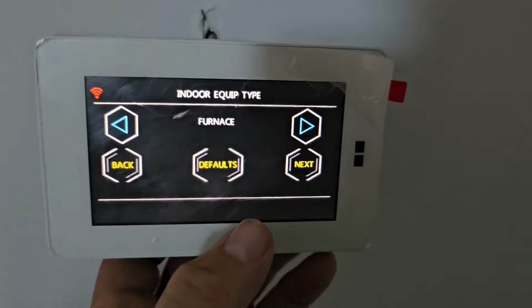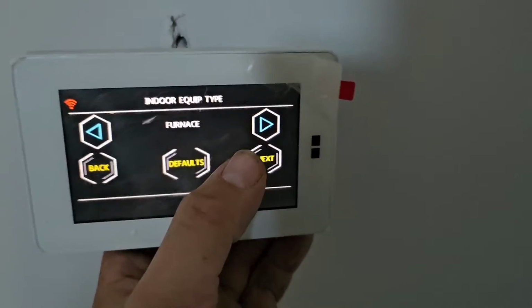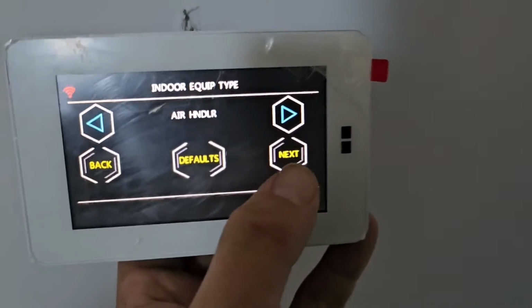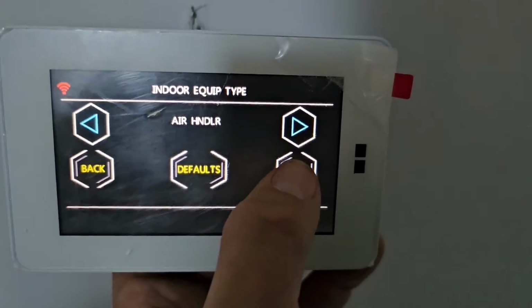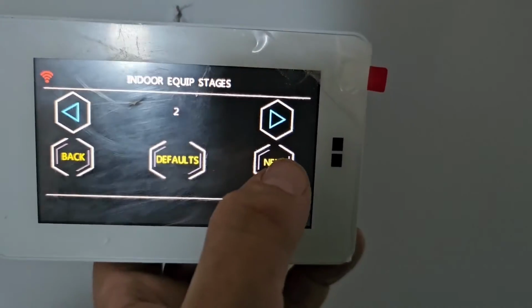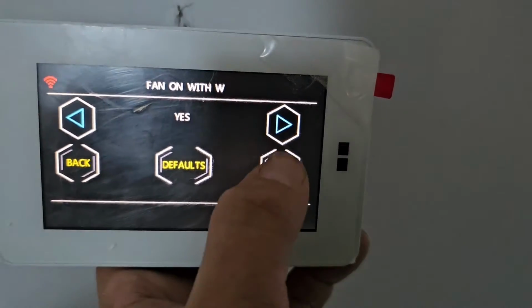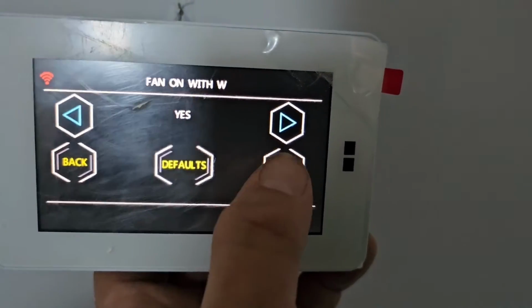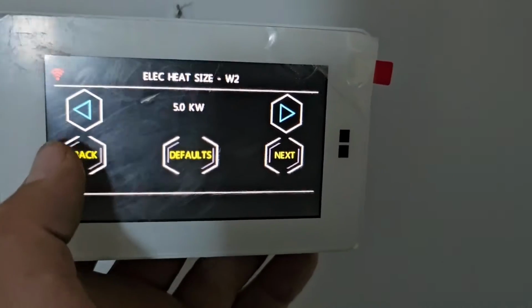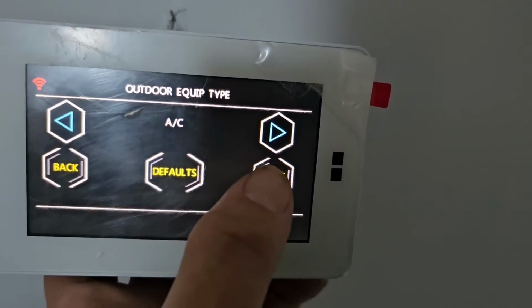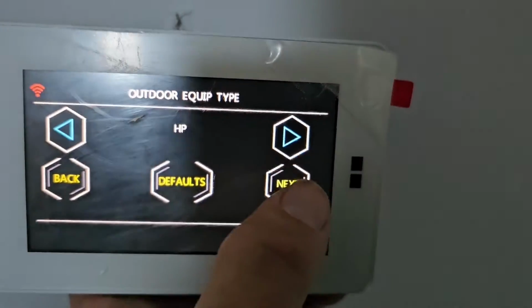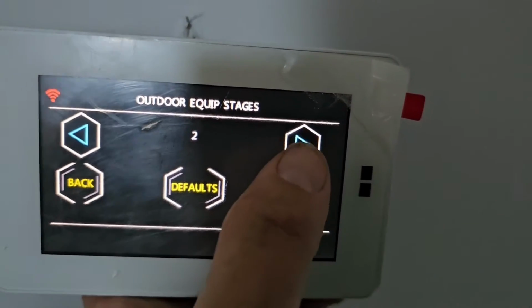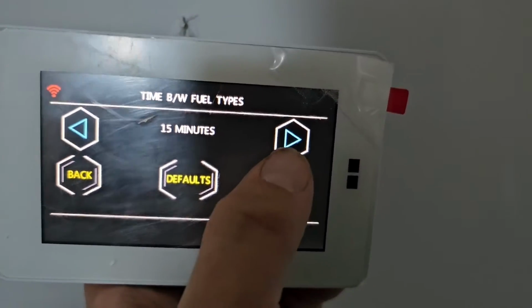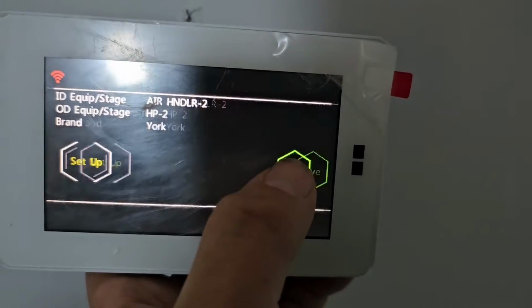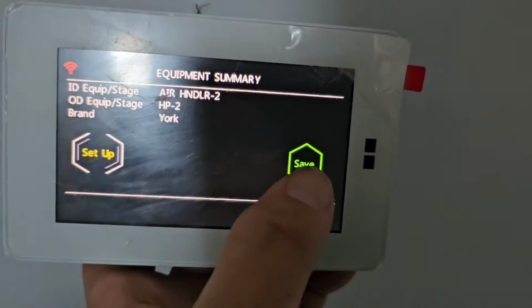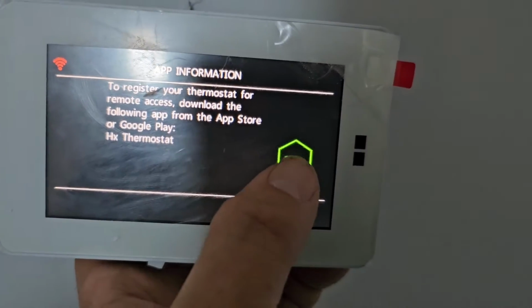Now, since we don't have a communicating system, we're not going to use auto setup. Indoor equipment type, it's an air handler. Equipment indoor stages, 2. Fan on with W, of course. Oh, no, we'll just roll with that for now. Outdoor equipment type, it's a heat pump. Outdoor equipment stages, 2. Sure. All right. Save.